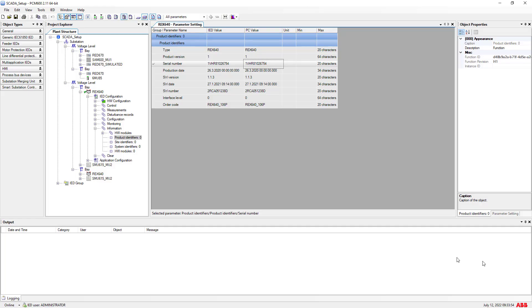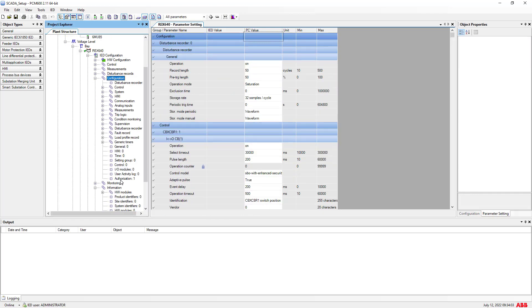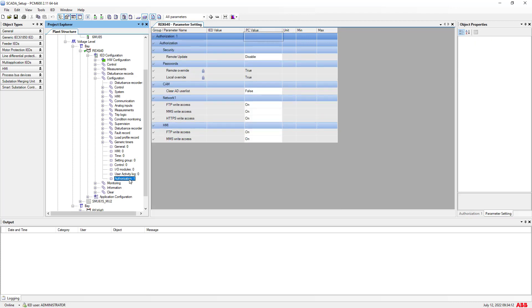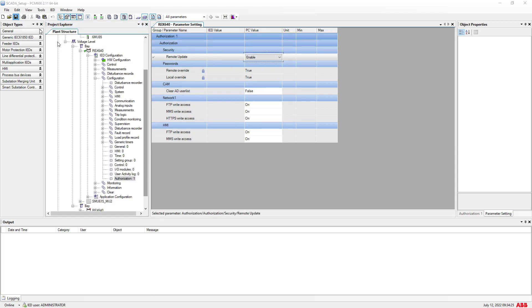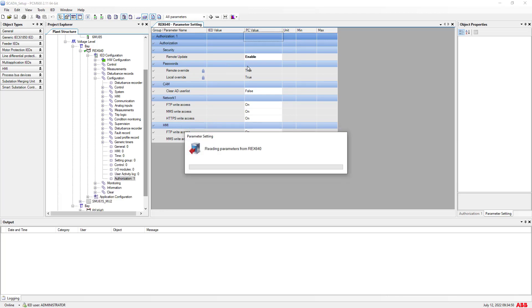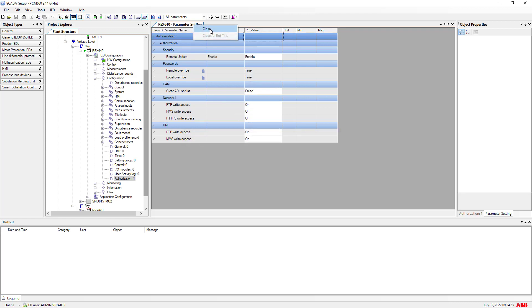Before you update the firmware, it's important to enable firmware update from remote. Expand the configuration section and the function group — under that you will see the authorization menu. Right-click and go to parameter setting, where you can enable the remote update option. Save it, then write this setting partially to the IED. PCM600 gives you complete flexibility to write specific changes from one function group. The remote update has now been enabled in the IED from PCM600, and we can close the parameter setting.